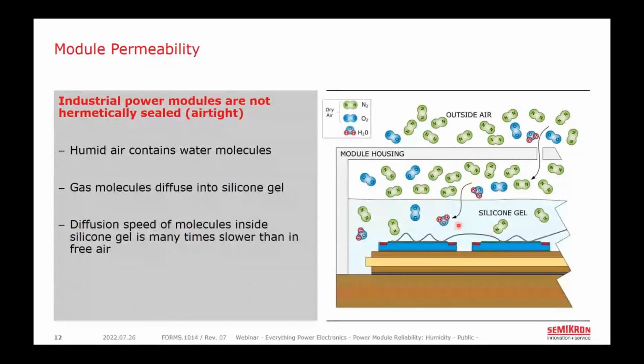Silicone gel is installed inside a power module to provide electrical insulation between conductors. Now, most people think of silicone as being impervious to water, and certainly silicone can stop the flow of water in its liquid state, as anyone who has caulked a bathtub with silicone sealant knows. However, what is less apparent is that any low molecular weight gas, such as water vapor, will diffuse into silicone gel and move around just as it would in air, albeit at a much slower rate. Now, I wouldn't characterize the water molecules as being trapped in the silicone because they can move from the gel back into the air. But because of this difference in speed, as well as the two mechanisms I'm going to describe on the next slide, once the water molecules have diffused into the silicone, it will take some time to get them out.